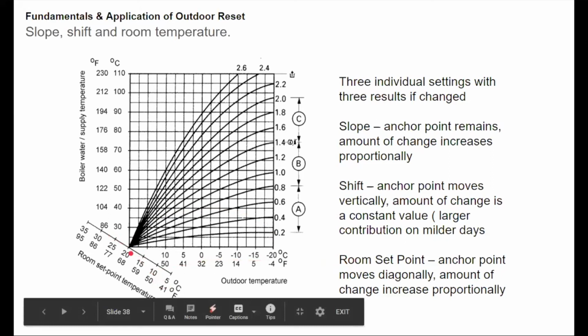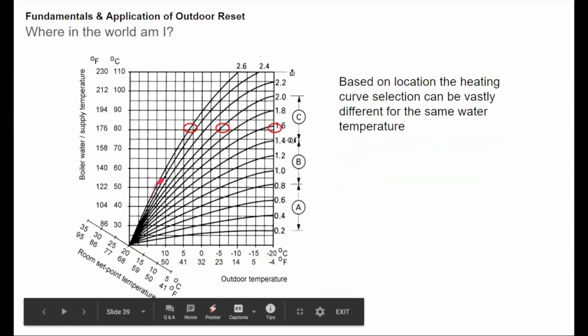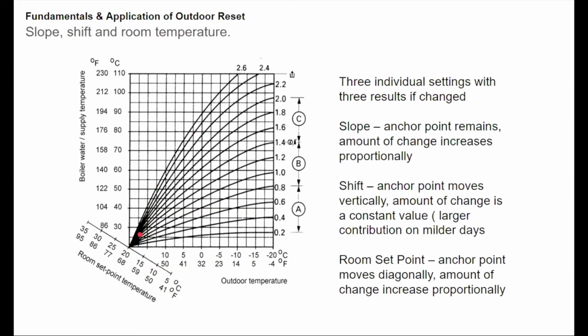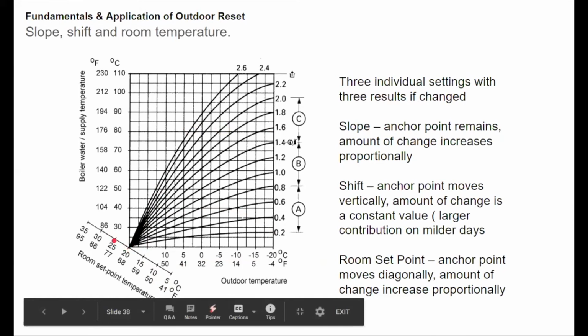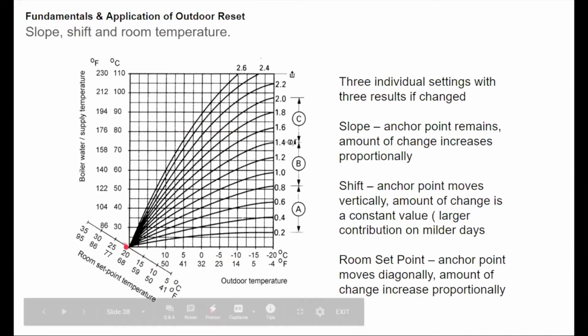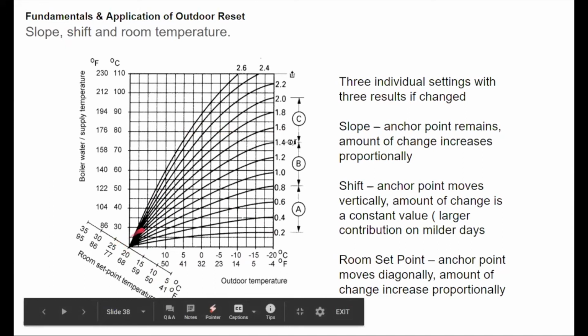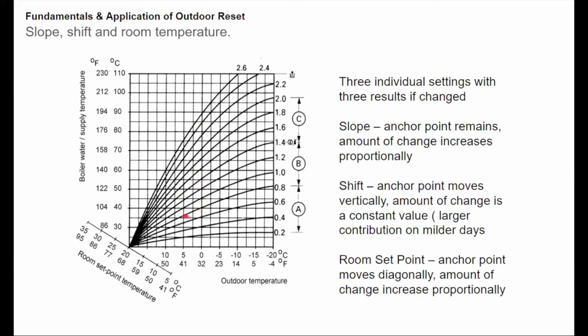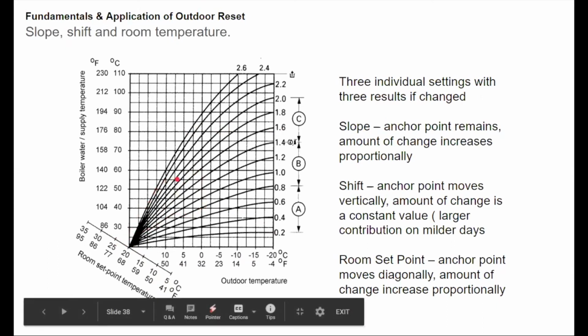This happens to be this curve over here. So what I'm doing is when I make a room temperature change, I'm grabbing this fan of curves, this series of curves, and dragging that point up or down, which effectively will change the room temperature set point. So if I drag that whole fan up, the ratio change stays the same, but it's going to add up because it's tied in here. That ratio change is now corresponding to a 25 degrees Celsius room temperature or 77 degree Fahrenheit temperature, not 68. But the end result is if I change the room temperature here, that proportionality stays the same, and the room temperature should stay constant from a mild day to a cold day.